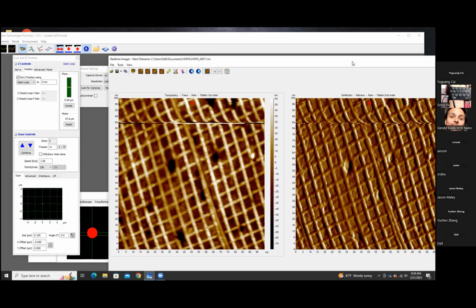So what we're going to do is, if you go back to your servo control window for your Z position, and you look at where it says 0 nanometers, just type in some abnormally, obnoxiously high number. Just hit 99999, enter. What that's going to do is default it to the highest possible position. So if you go back to your Z out and you measure again, you should be somewhere around 220 volts DC. Okay, I'm measuring Z out, and my range on my voltmeter is 1,000 volt, and I read minus 217 volts.